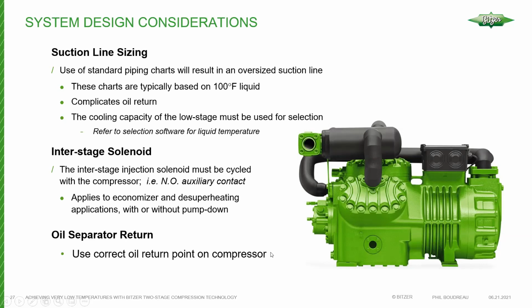Be careful with the suction line standard piping charts if that's what you're using, because most, if not all of these, are based on 100 degree Fahrenheit liquid. And again, if you're subcooling refrigerant, the capacity of each pound of refrigerant is totally different, and it really skews the numbers. So what can happen, just to keep this simple, is if you use standard charts based on 100 degree Fahrenheit liquid entering that expansion valve, you're probably going to end up with an oversized suction line as well.